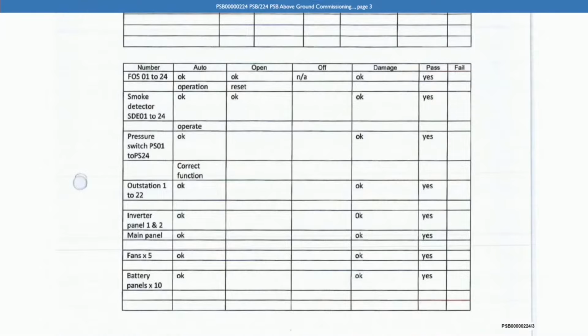At the bottom of that page, in the larger table at the bottom, we can see that for pressure switches, this is three items down, it says pressure switch PS01 to PS24. Is it right that the only information in the commissioning report in respect of the pressure switches is that we've got auto operate okay, so that it operates okay, yeah, and then damage okay, and then pass yes. Do you see that there? Yes.